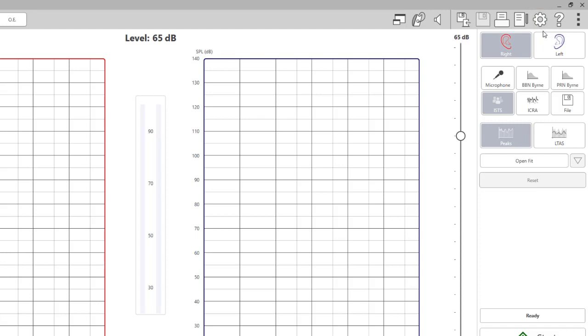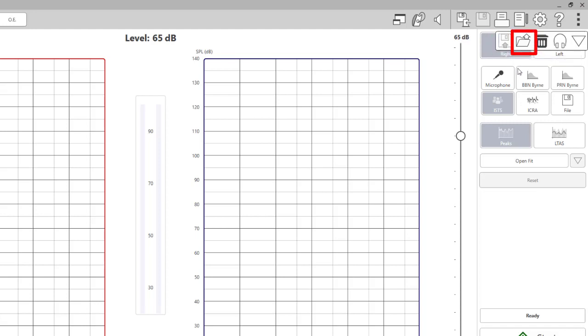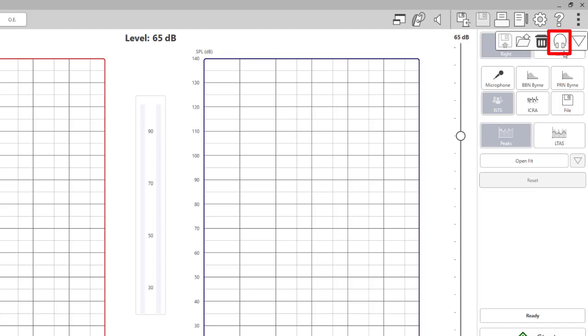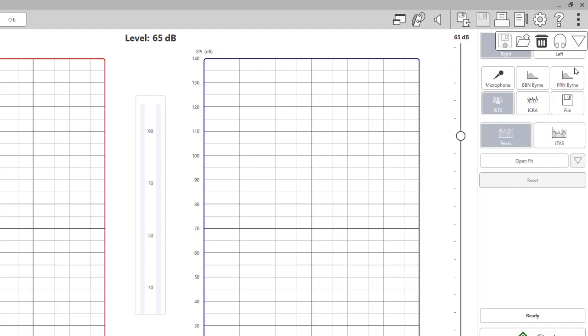Click on the last icon in the top right corner. This is the more icon. From here you can save the current session or open a session from a file. You can also clear previous data for the current test. The old session or test will be saved in the previous session. You are simply clearing the screen for the current test. The headset icon is for the probe monitor option. You will need to connect a stereo headset to your REM system to use this option, but when this is enabled you can listen to what's happening at the probe tube while it is in the patient's ear. The triangle icon will give you access to system calibration information. You can view existing calibrations, load calibrations for a new system, or from your annual calibration, or if you replace or get new probe microphones.